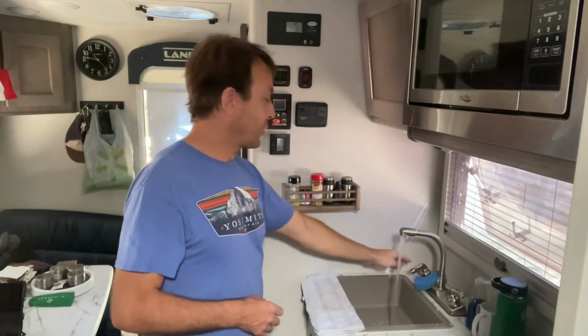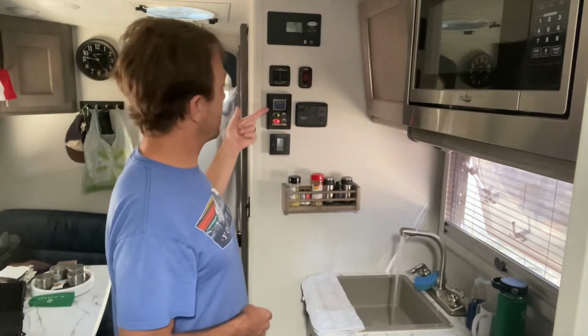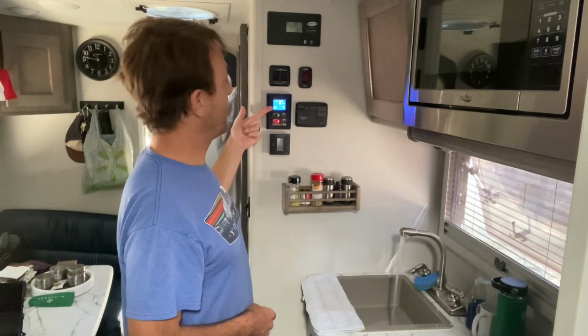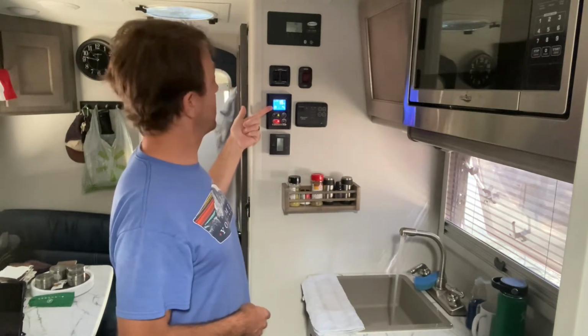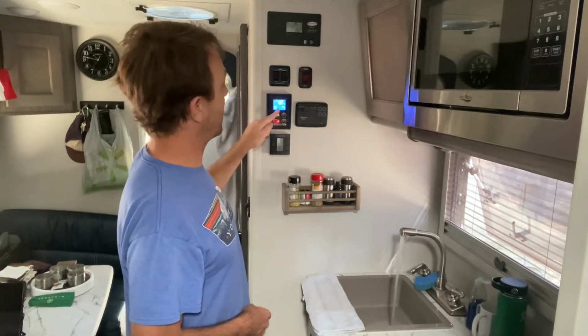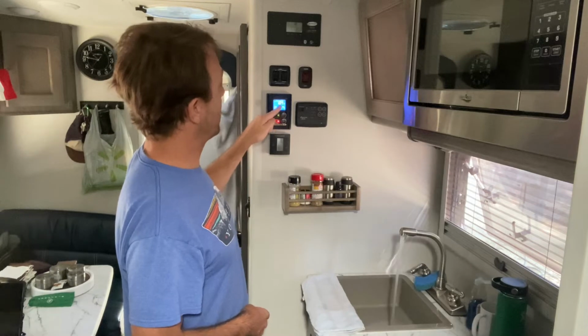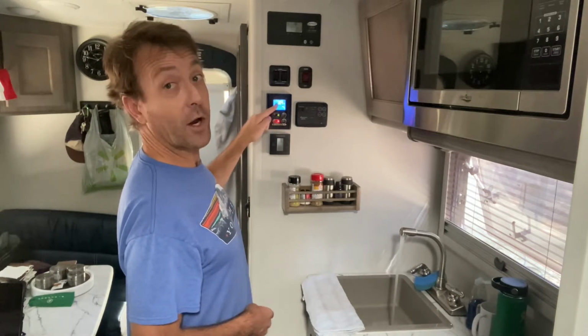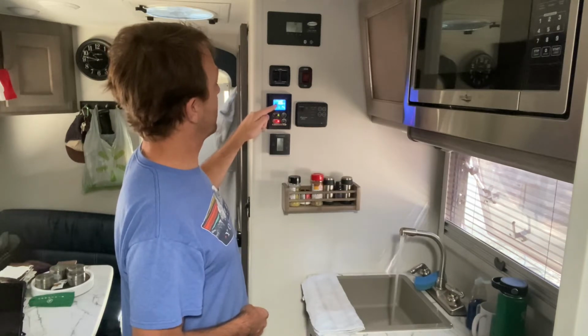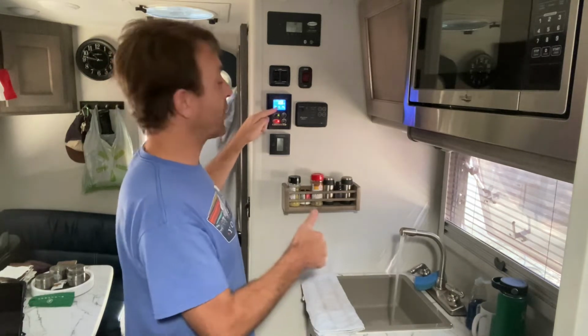So now you can see that it'll fire, and the temperature will adjust. It tells you the fan's going, it's got the flame going, water's running. Remember, we had it set for 112, so it's 106 now, 108, so it's increasing.